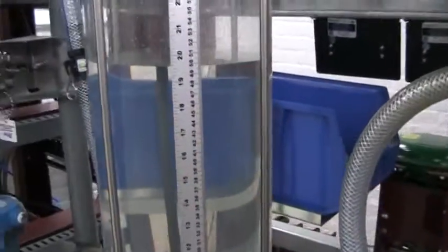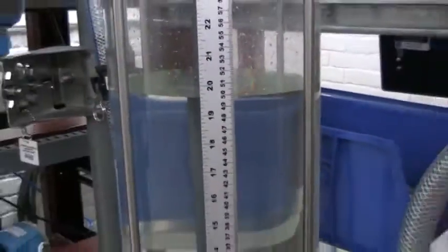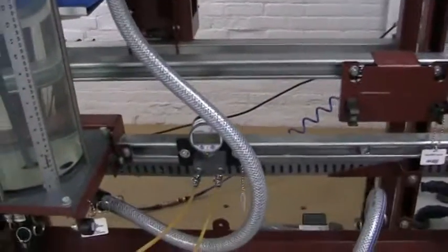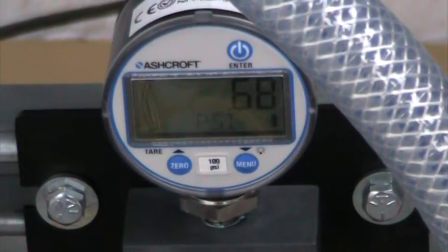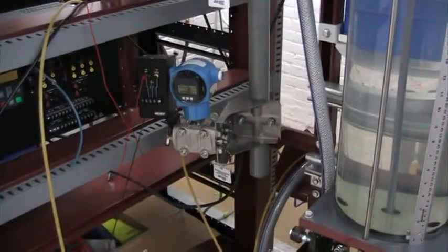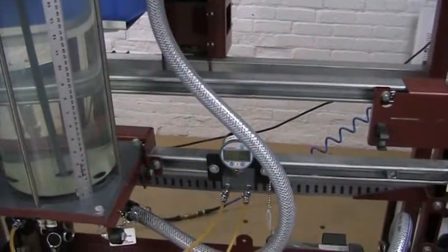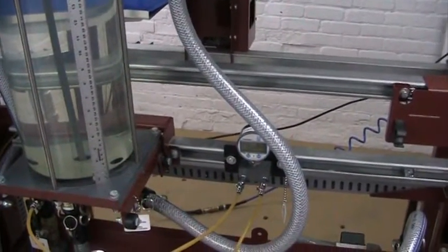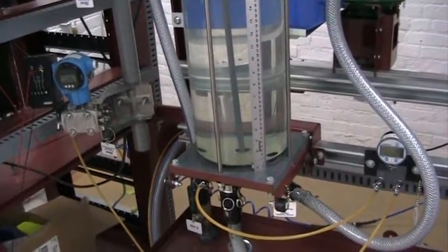So I'm approximately here at 50. I'm not quite at 50, but approximately. So I'm just going to go back and take a look at my readings. 0.68 psi. 0.698 psi. Fairly close. They're a little bit off, but fairly close. Again, if you have to do something like this, then you would need to be more accurate than what I have here. Both have to have the same exact value.